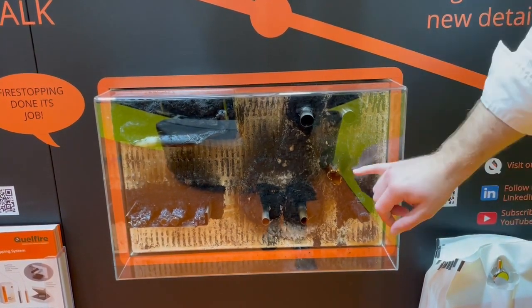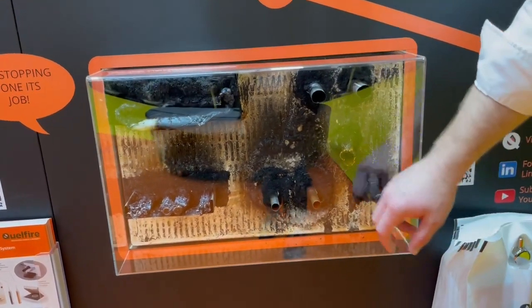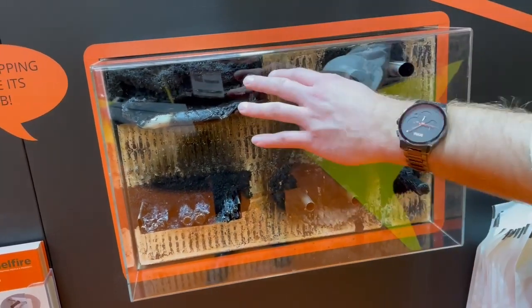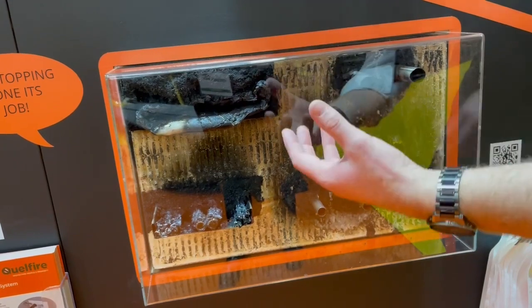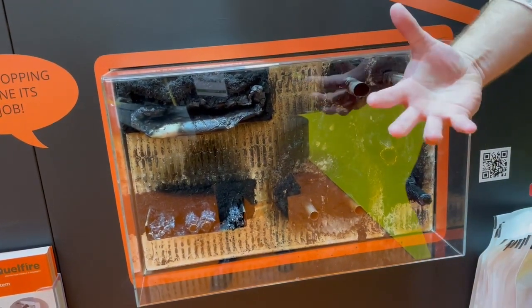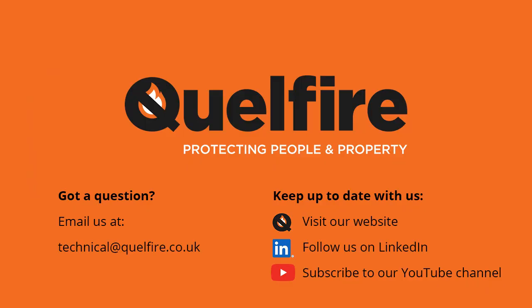Further examples here: more insulation materials and also a plastic ventilation duct. You can see very clearly there the plastic being crushed by the expanding intumescent, ultimately filling that metal sleeve with a solid carbonaceous char, preventing the fire from penetrating through the compartment wall.